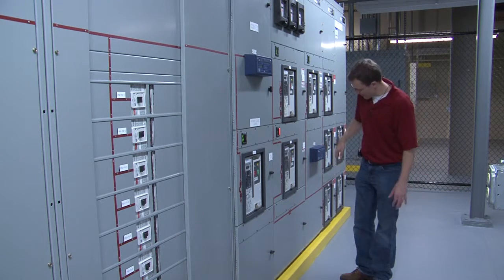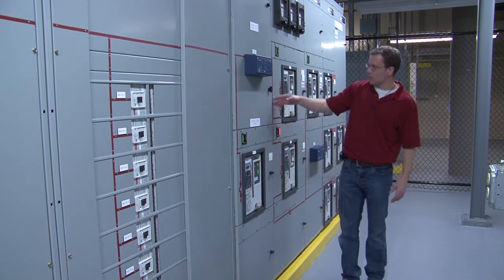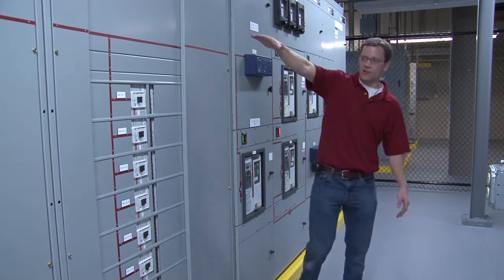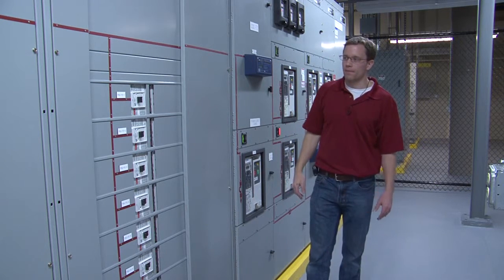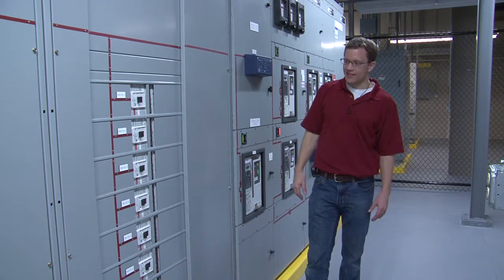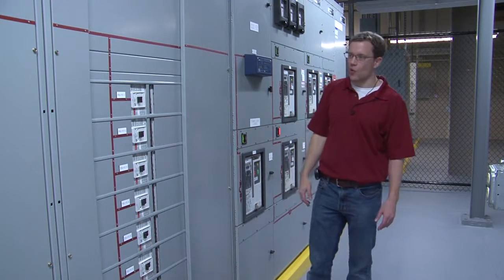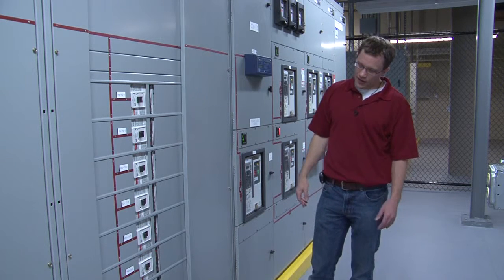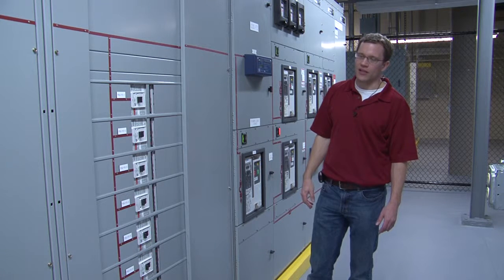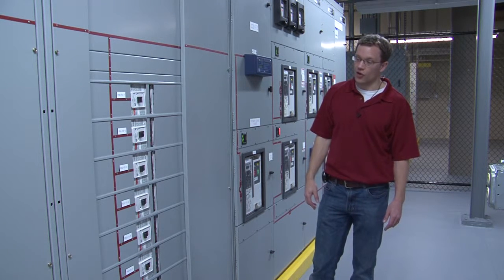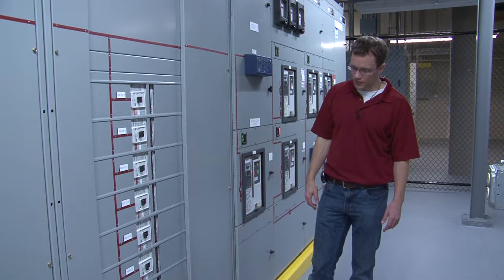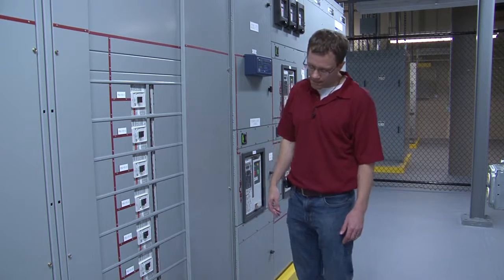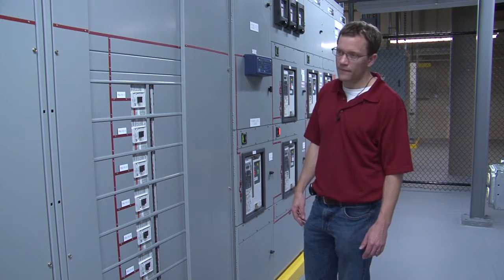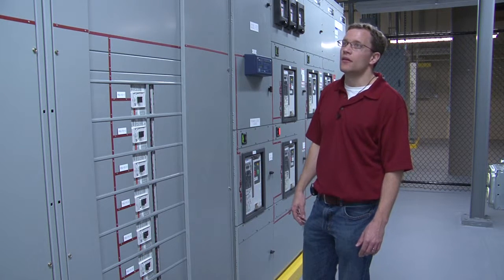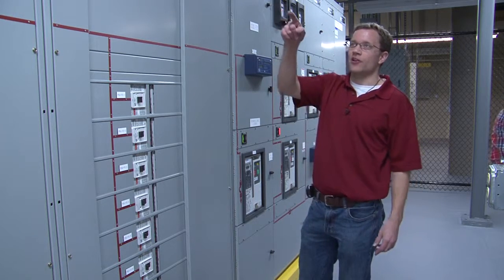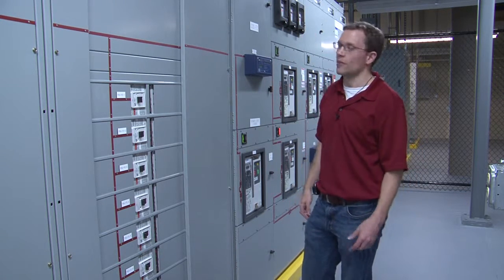So normal power flow, like I said, comes from the 5 breakers, comes through this breaker, comes up here, hits the main bus, and then this is what feeds the input to all the PDUs on the data floor. In this case, for this system, I think it can feed a total of 24 PDUs. There's breaker provisions for that. At this point, there's only 7, I believe, that are installed. They may have added some since I was last here, but from all I know, that's how it is. Overhead, there's a breaker lift, the same as the one at the UPS input substation. It can be used to take any of the breakers out.